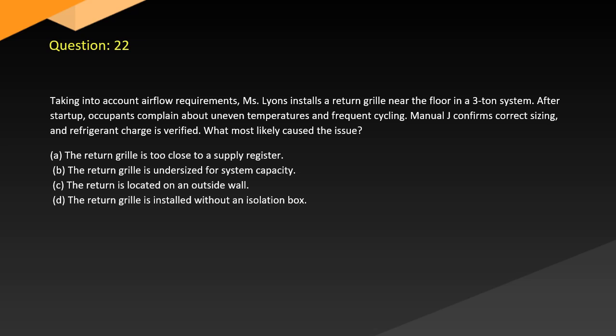Question 22. Taking into account airflow requirements, Ms. Lyons installs a return grille near the floor in a 3-ton system. After startup, occupants complain about uneven temperatures and frequent cycling. Manual J confirms correct sizing and refrigerant charge is verified. What most likely caused the issue? A. The return grille is too close to a supply register. B. The return grille is undersized for system capacity. C. The return is located on an outside wall. D. The return grille is installed without an isolation box.